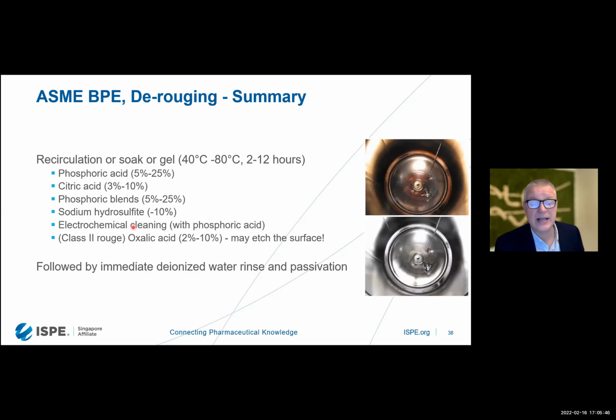Electrochemical cleaning or oxalic acid is etching the surface, so that is not good for the surface finish. Electrochemical cleaning is a little bit complicated because it's not only the phosphoric acid, you need electrodes in the system, and it could be a little bit complicated to accomplish this.